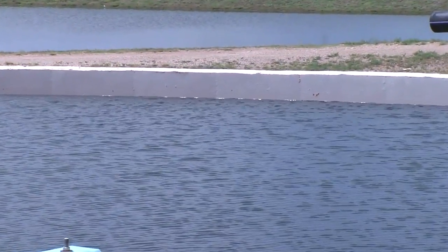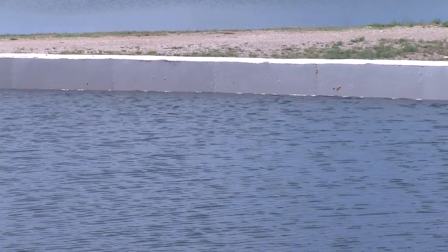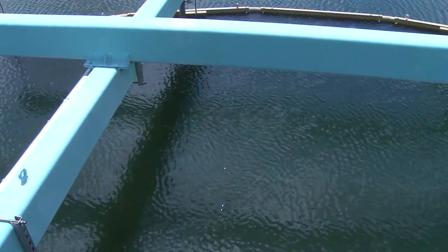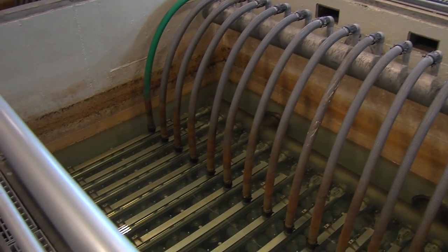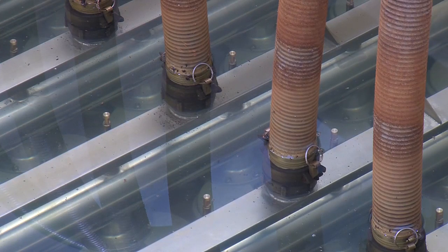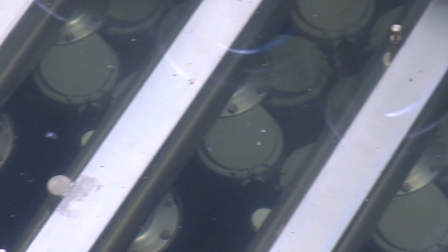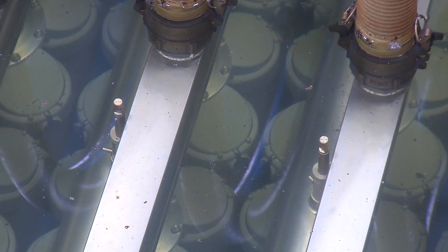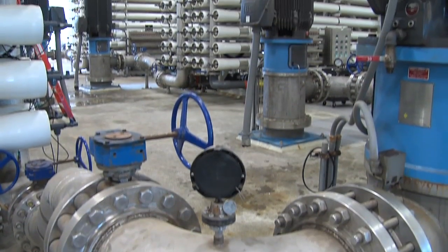Once inside the water treatment plant, a coagulant — ferric sulfate — is added. This brings together any material still suspended in the water, which sinks to the bottom for removal, producing very clear water that smells like lake water. A few hundred yards away, the water passes through a series of microfilters consisting of 4.5 million microfiber strands, removing destabilized particles, protozoans, viruses, and bacteria before the reverse osmosis step.